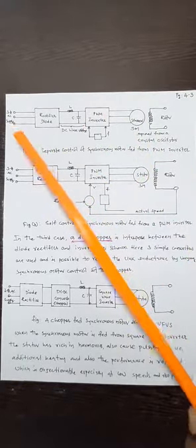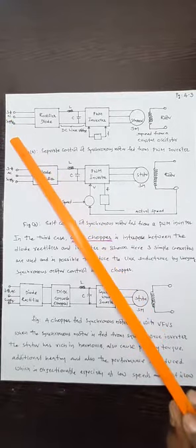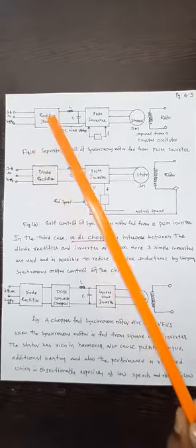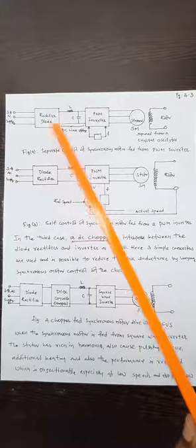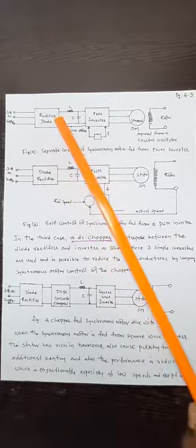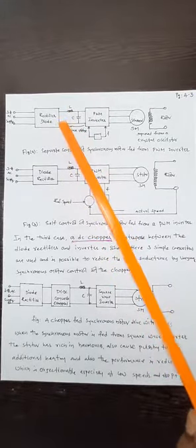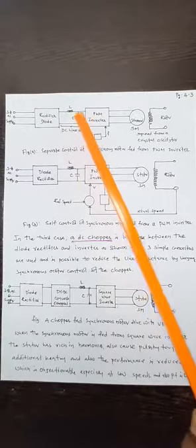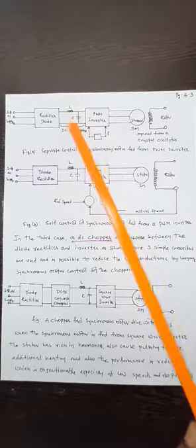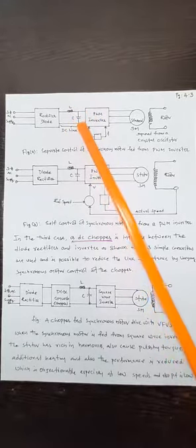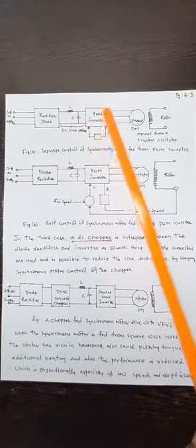So what is the principle here? Three-phase AC supply is fed to the diode rectifier. It converts the three-phase AC into DC, so it is a constant DC. This DC is forwarded through a filter for improvement, or purification, of the waveform, and then fed to the PWM inverter.